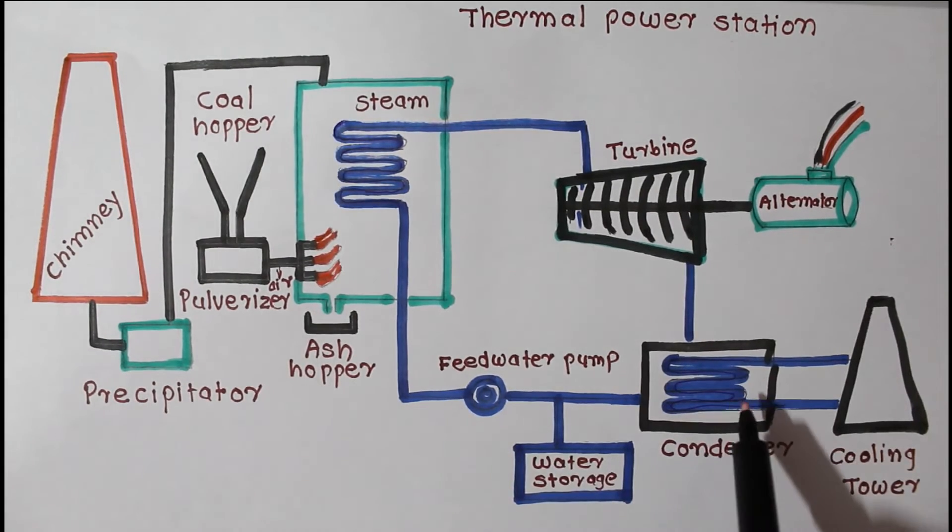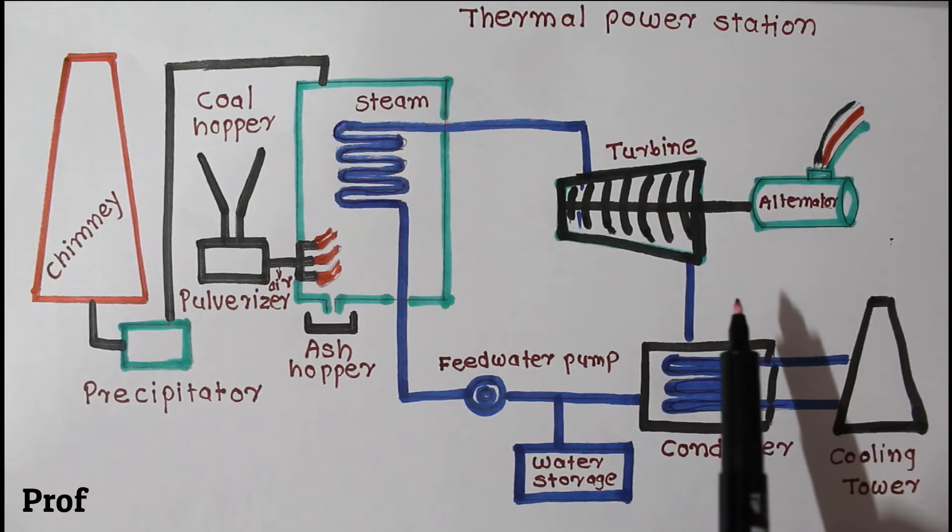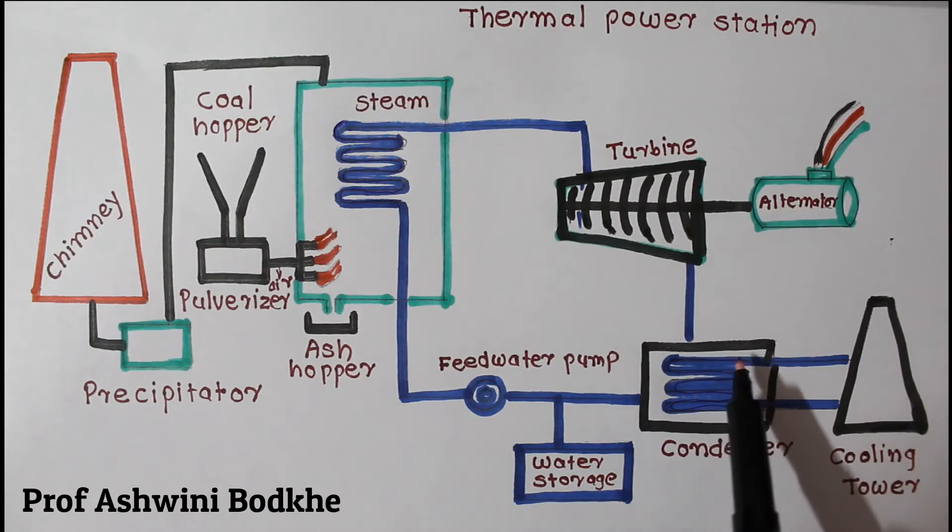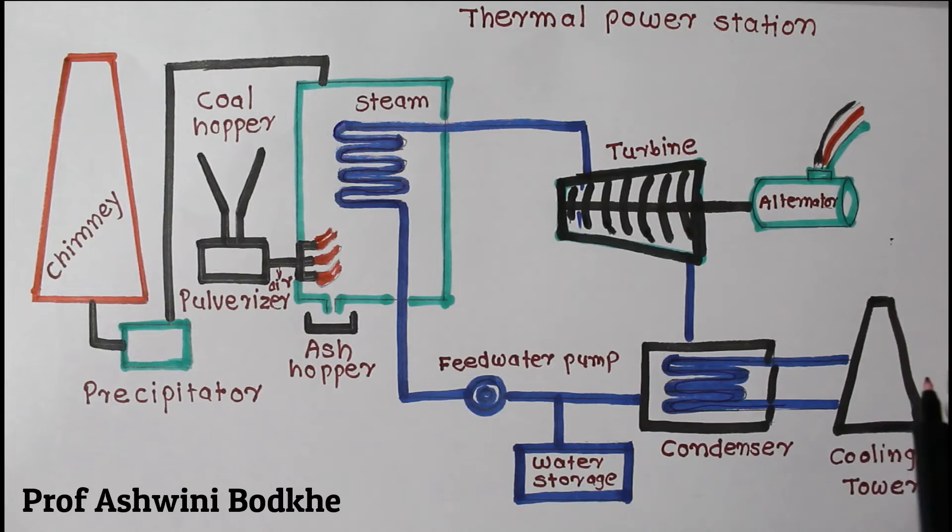Condenser. The surface condenser is a shell and tube heat exchanger where cooling water flows through tubes and exhaust steam is fed into the shell around the tubes. As a result, steam condenses outside the tube.